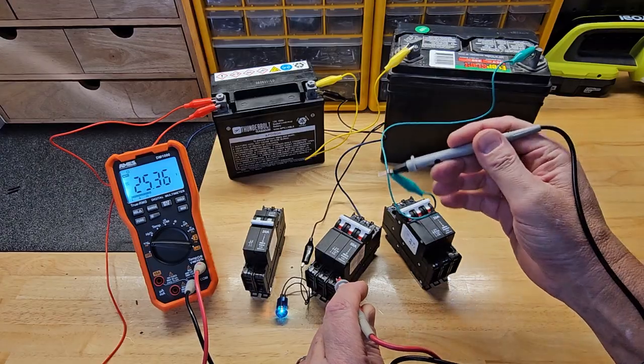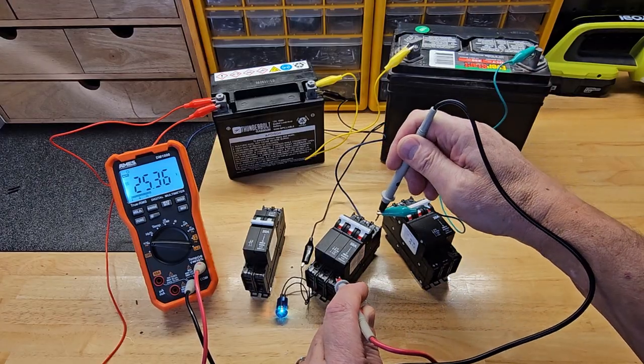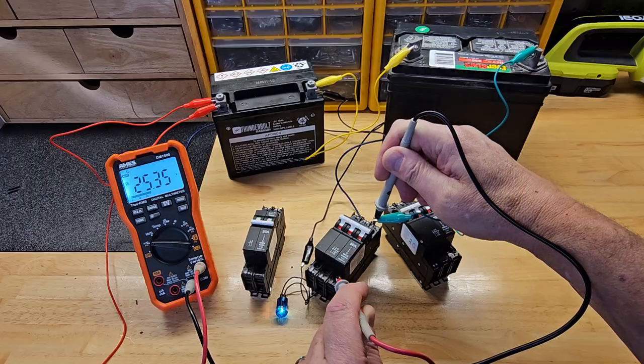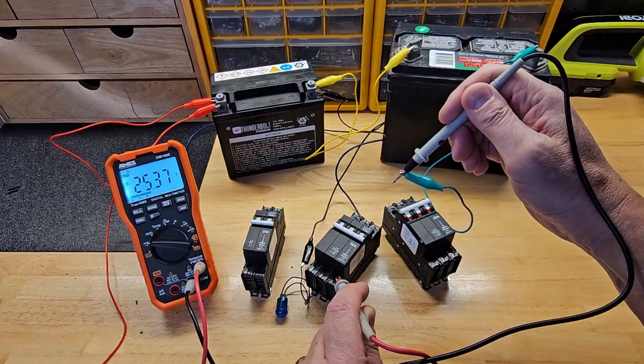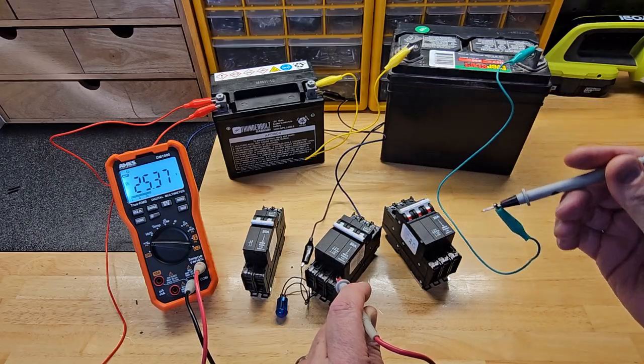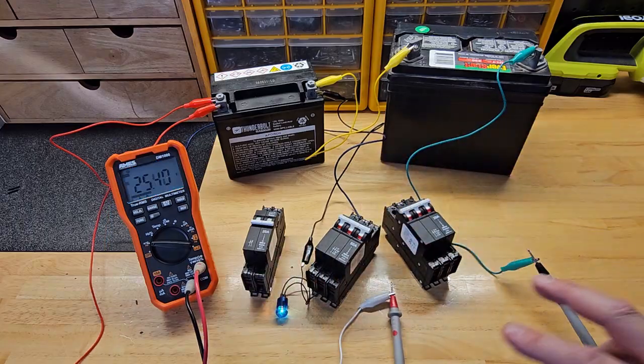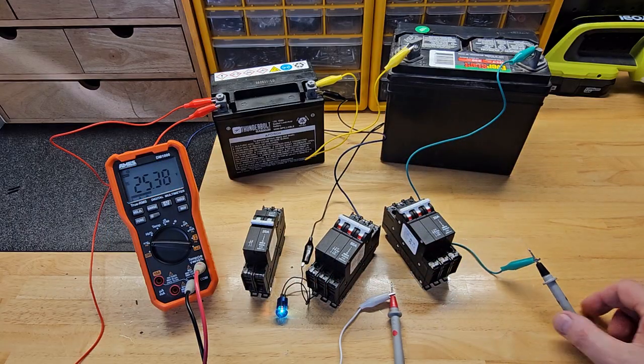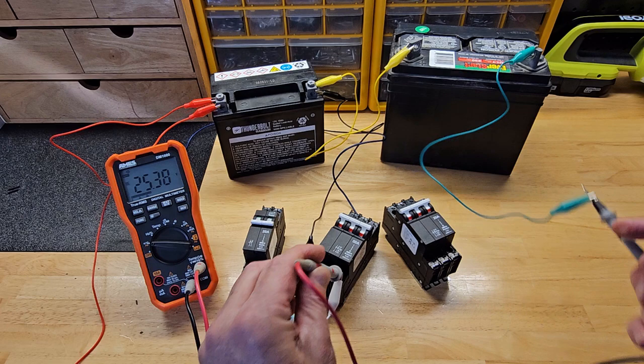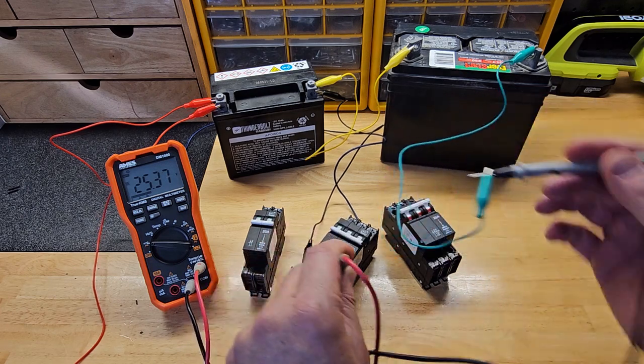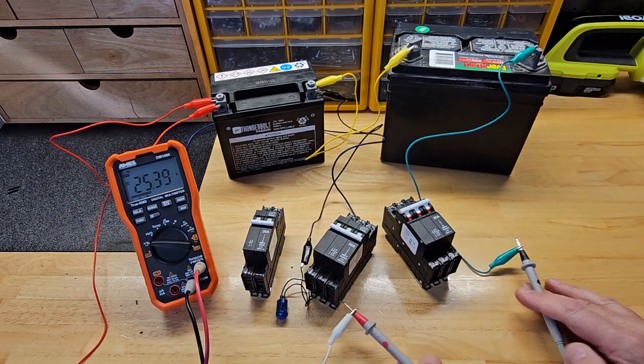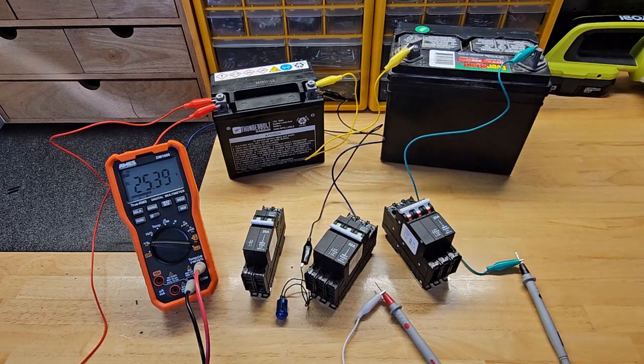The circuit trips immediately, and it is a pulse, so you just need to apply a quick pulse and it will trip the circuit breaker. But you can see how handy this shunt trip is, because if you want to cut the circuit remotely, you just apply 24 volts to that coil and it shuts down immediately.